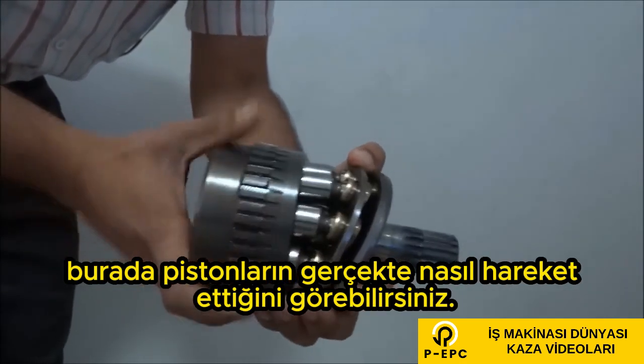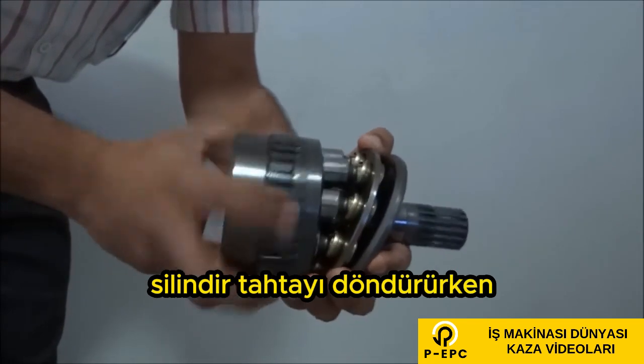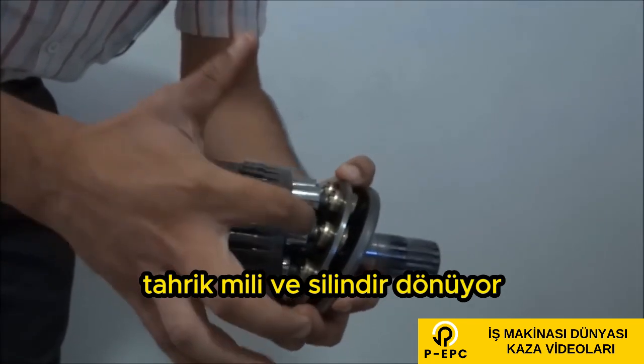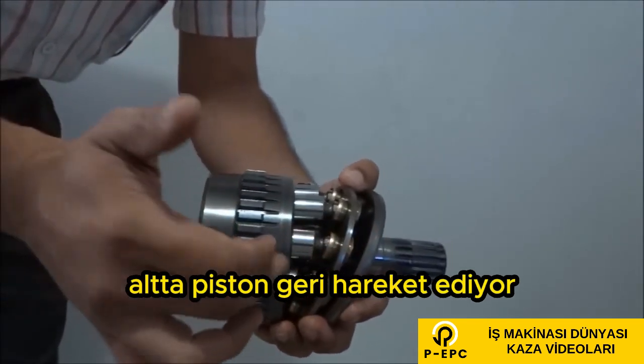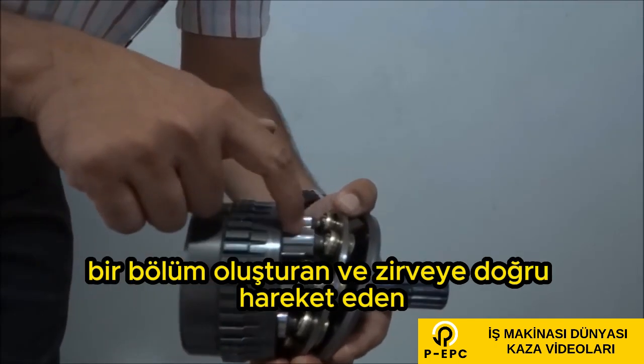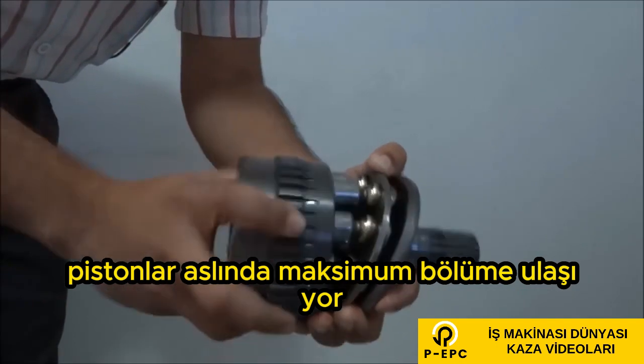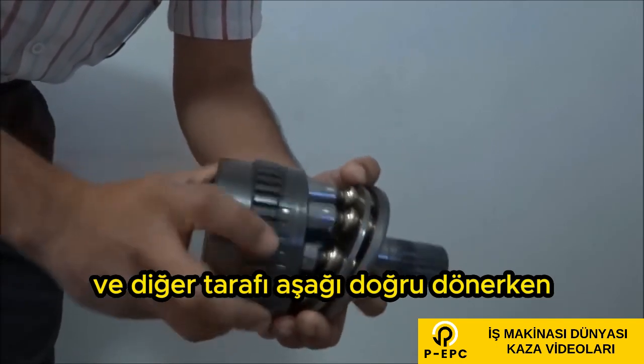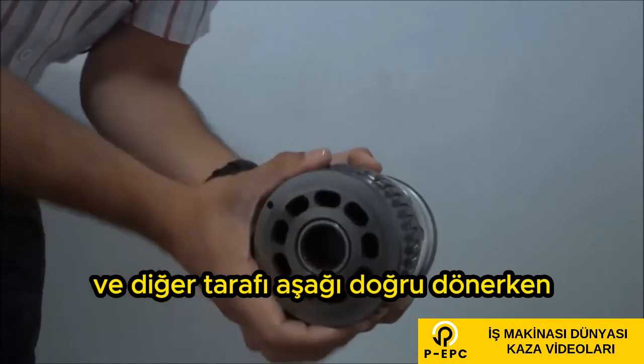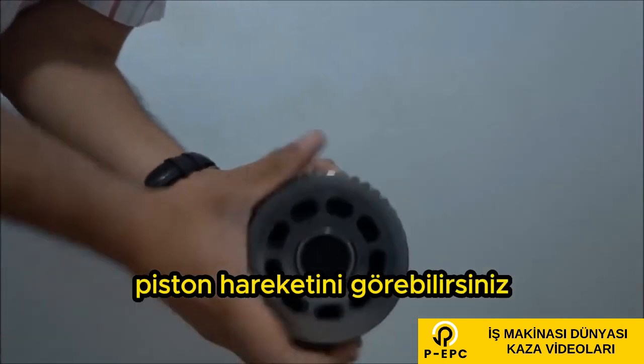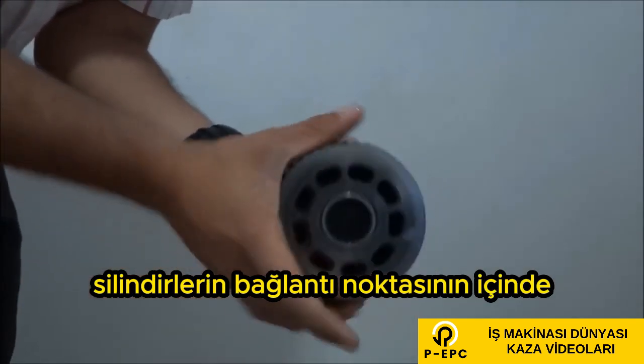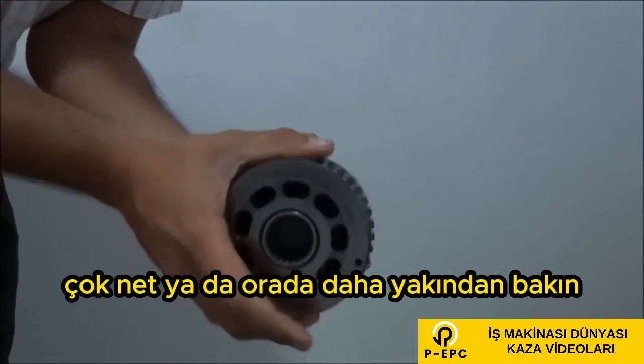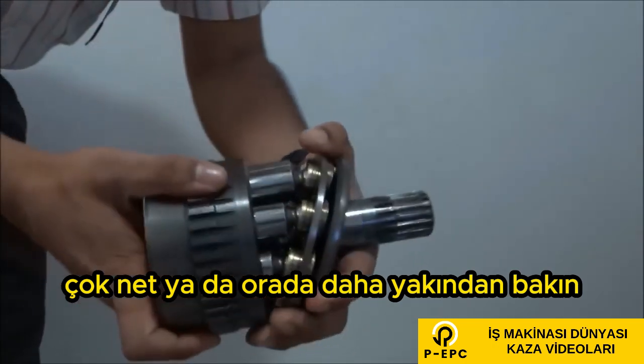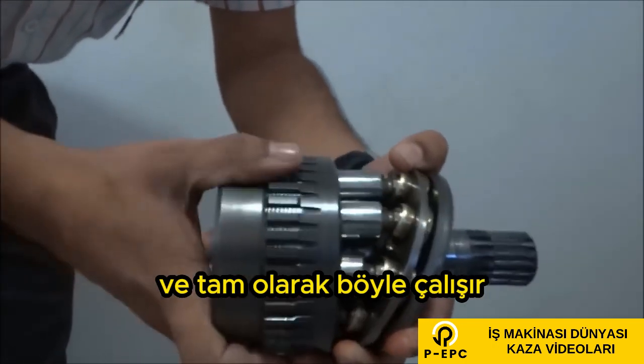So here you can see how the pistons actually move as the cylinder rotates. Both the drive shaft and the cylinder are rotating. At the bottom, the piston is moving back, which is creating a suction, and moving towards the top, the piston actually reaches the maximum suction, and as it rotates to the other side downwards, the delivery is happening. You can see the piston movement inside the pot of the cylinders very clearly over there. Have a closer look, and that's how it exactly works.